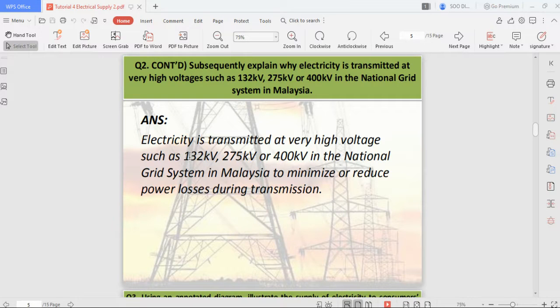So you can transfer it at 132, 275, or 400 kilovolts, depending on how much electricity you generate. If you're generating a lot of electricity, you want to go for a very high kilovolt transfer. So remember, one reason is to reduce the power loss.